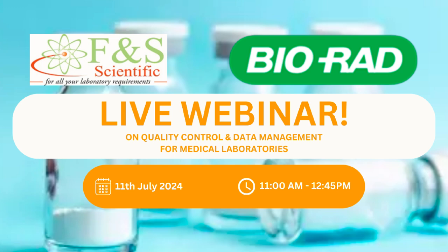You're using patient samples, but when you do patient samples, there is also a formula for the same. If it's quantitative, you compare what is the acceptable value, acceptable TEA, total allowable error, that you'll get from Westgard. I don't know if my colleague will mention the same, but when you want total allowable error, you can go to Google and just Google. For example, I'm just giving an example, troponin. They'll give you what is the total allowable error for troponin. So once you compare the two, plus or minus, it will give you a value that you'll use to measure if you're within or not within. If you don't find that test in Westgard, then Data Innovations will also give you the same. I hope I've answered your question. Thank you.